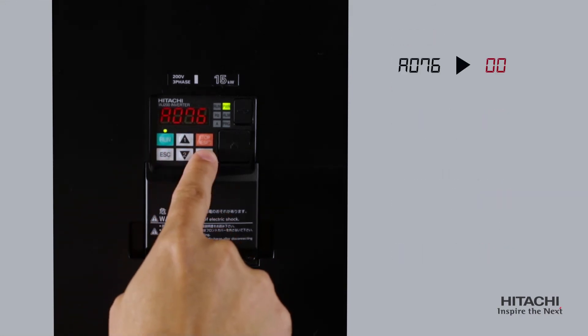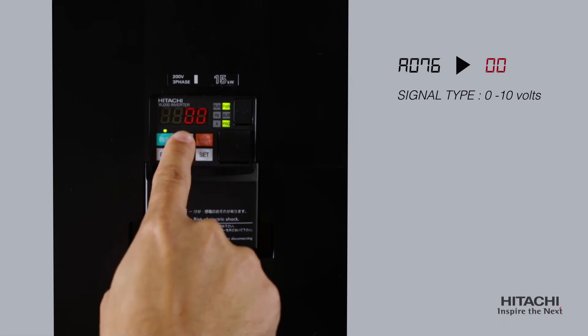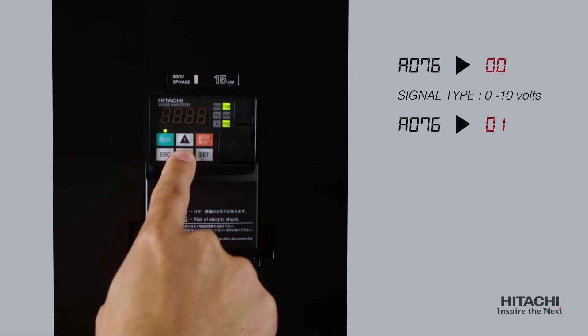A76 is the signal type selection. Please select a setting of 00 for 0 to 10 volts or 01 for a 4 to 20 milliamp signal type.